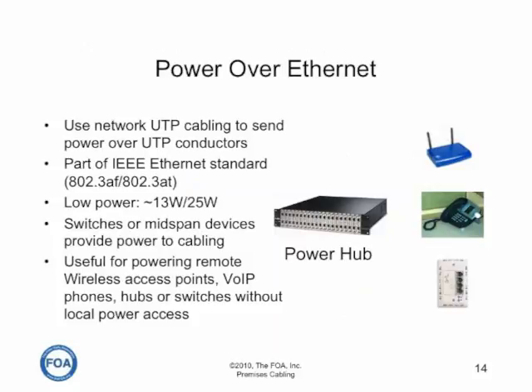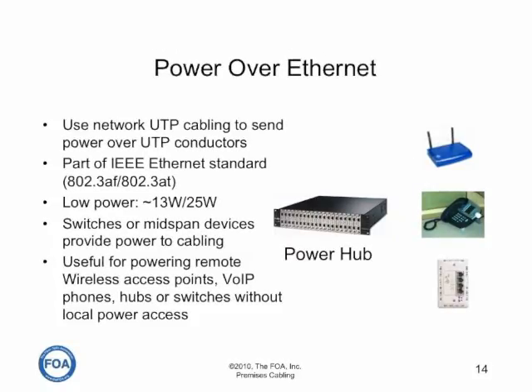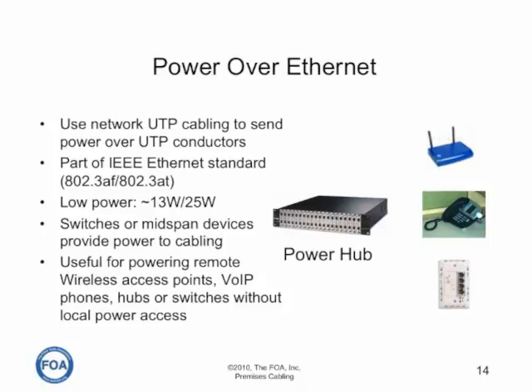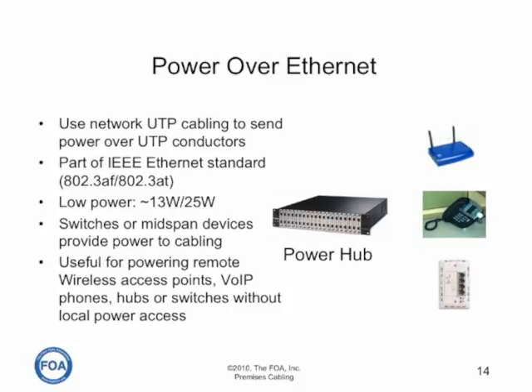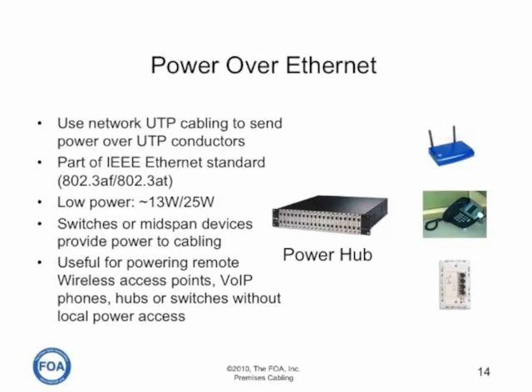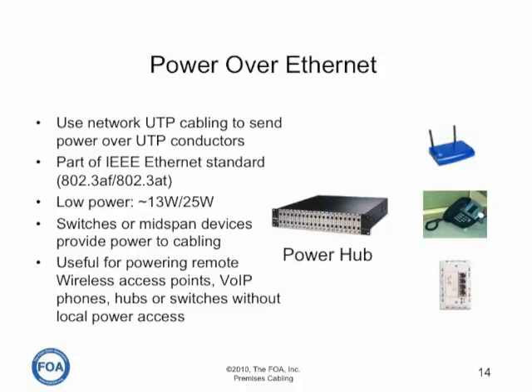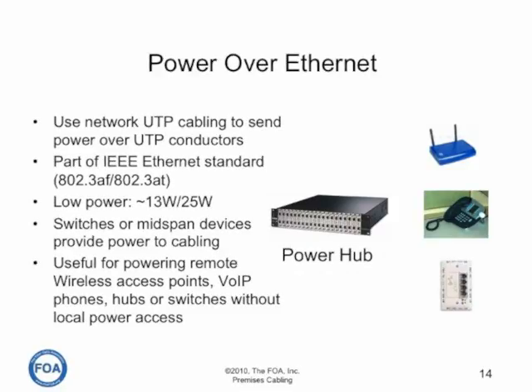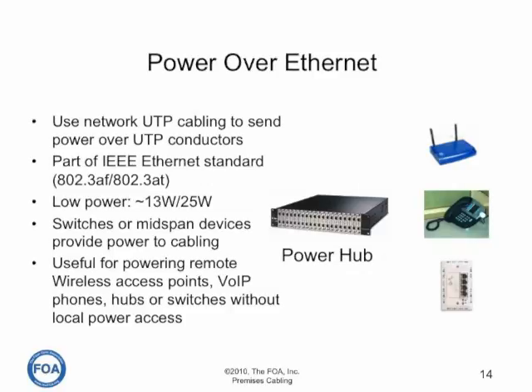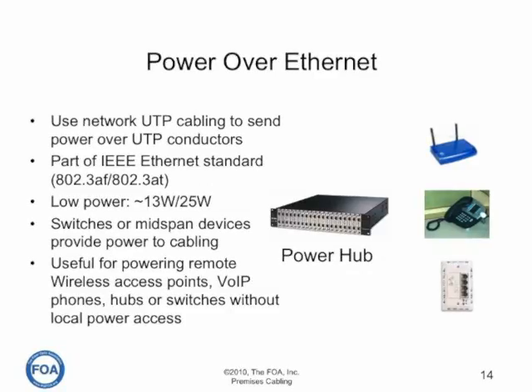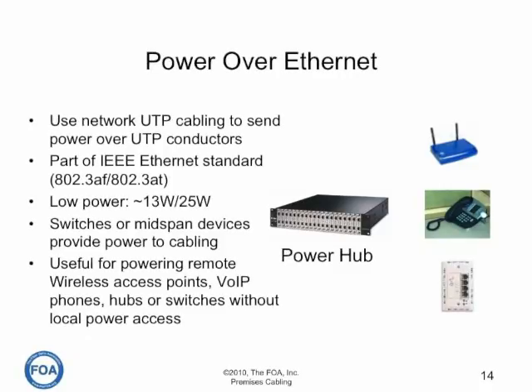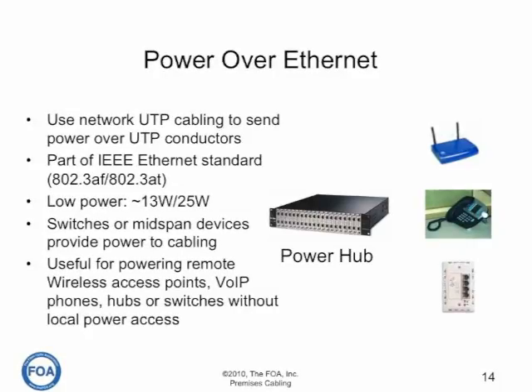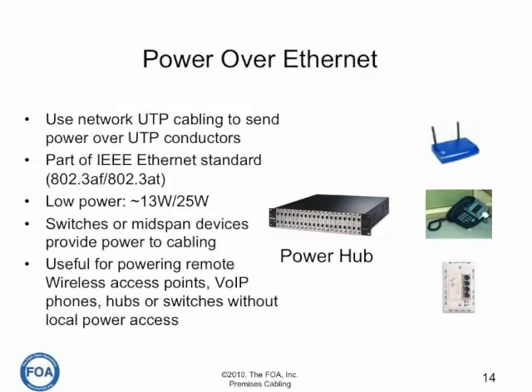One thing copper cabling can do that fiber cannot do is provide both power and signal transmission. Power over Ethernet is part of the IEEE Ethernet standard, not cabling standards, and provides for two different power levels — 13 watts and 25 watts of power — through powered switches or mid-span devices that provide power to the cabling. It's useful for powering remote wireless access points, voice over IP phones, hubs or switches, without local power access. But all of these devices must meet the maximum power output of Power over Ethernet, which is currently 25 watts, which means many devices will not work on Power over Ethernet and require local AC power.